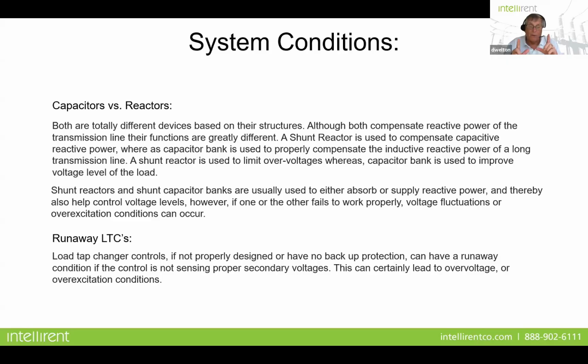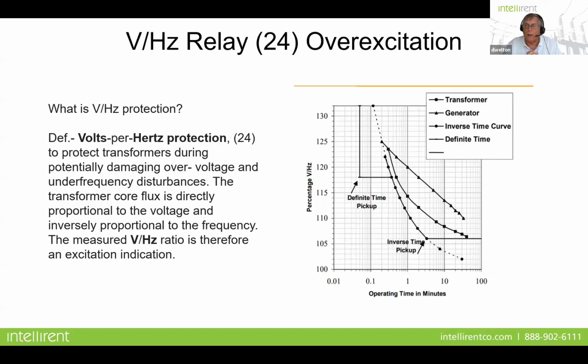Now we think of this as primarily an overvoltage reaction, but not necessarily, though that's true. Your overvoltage protection should keep this from happening. But if at the same time these voltage events or transients happen, and you have frequency fluctuation or a drop in frequency, you're going to have an overexcitation condition. So it's good to have a discussion with your relay engineers to perhaps involve or enable volts per hertz protection, not just for generators and GSUs, but also for your transmission line protection as well.